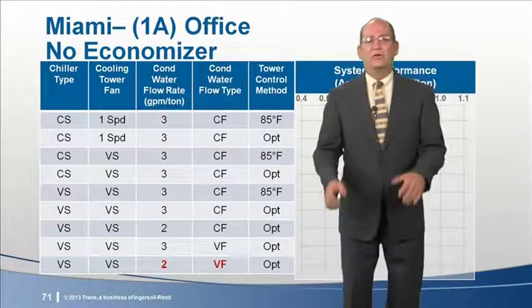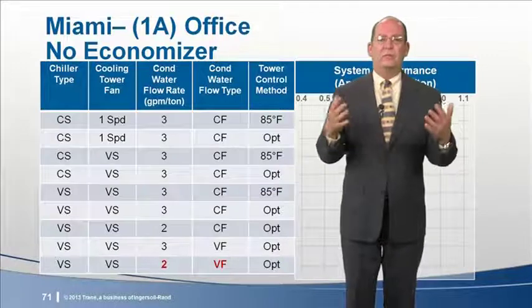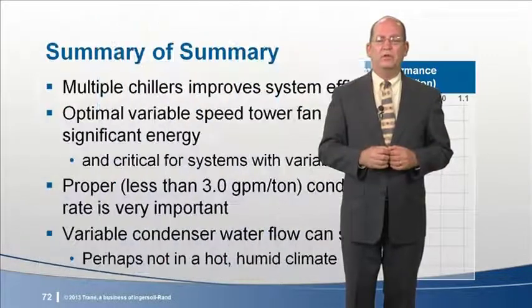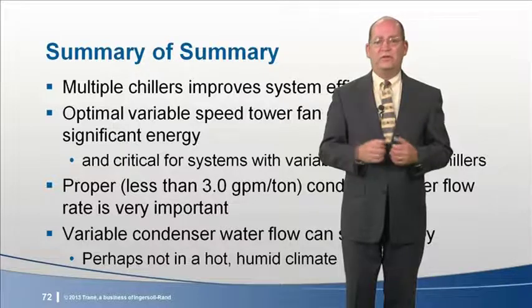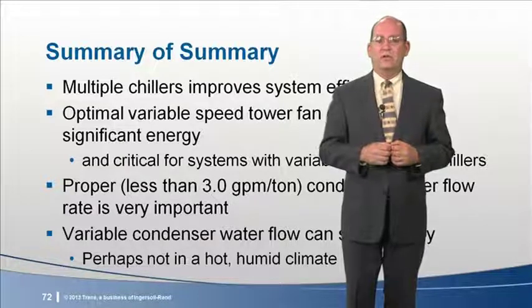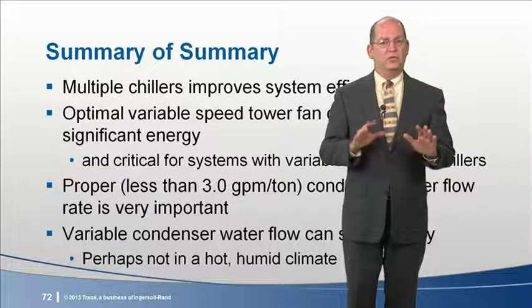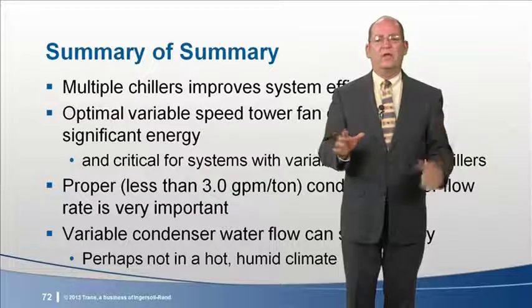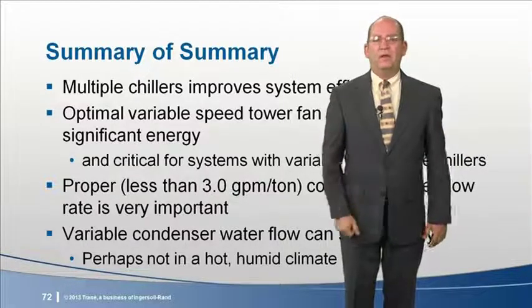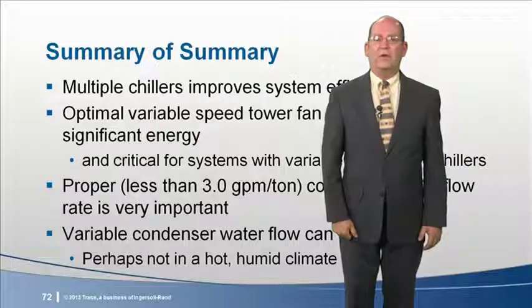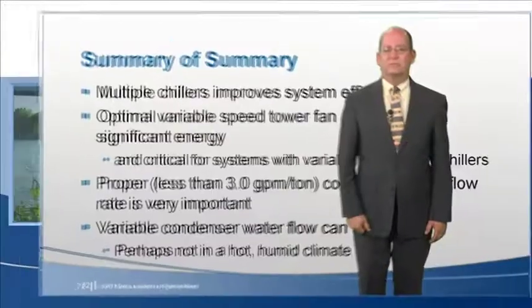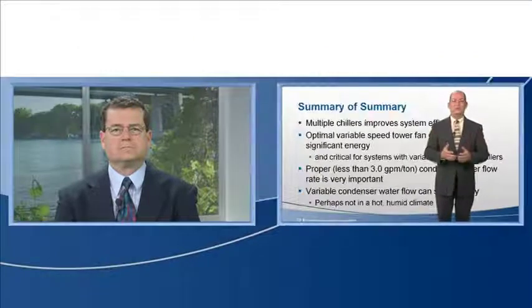However, there are virtually no savings from variable speed condenser water pumps. So after looking at this limited set of buildings and locations, the conclusions reached are the same as what was already covered. A possible exception is that variable condenser water flow rates may not save energy in very hot and humid climates. Lee, what's next?